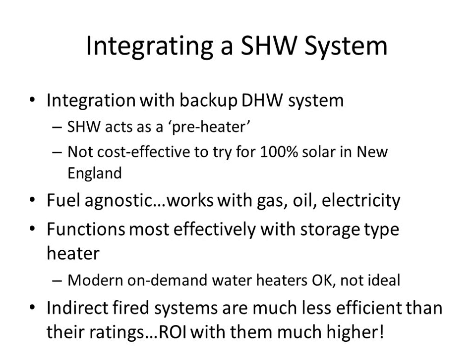And I think I mentioned before, when we go to on-demand or tankless systems, modern systems will work. Most of them require a tempering valve upstream of them before they go in. You have to be really careful looking at older tankless systems that are going through boilers, because a lot of those fire whenever they see flow. So when you look at systems that are 15, 20, 25 years old, as soon as you turn on the hot water, that boiler fires and just increases the temperature by a certain amount. So you're not going to save anything if you put a solar hot water system in.